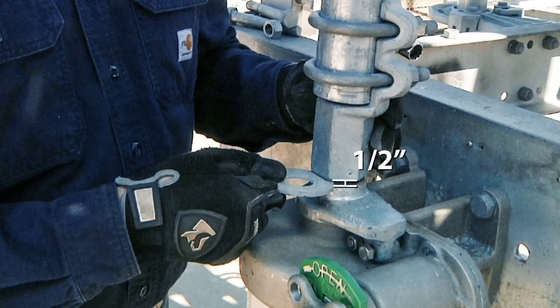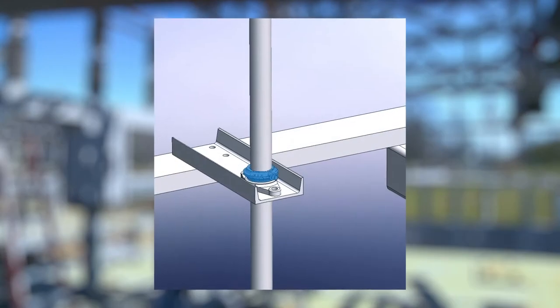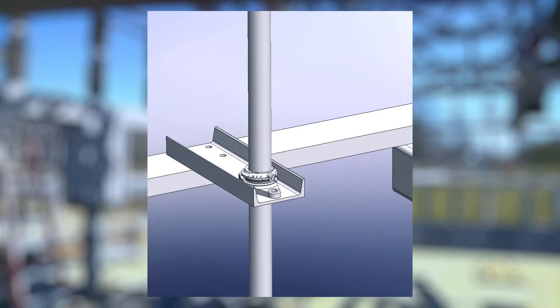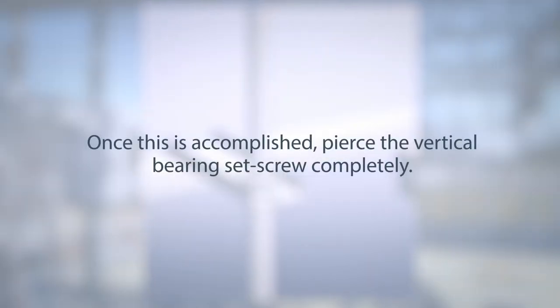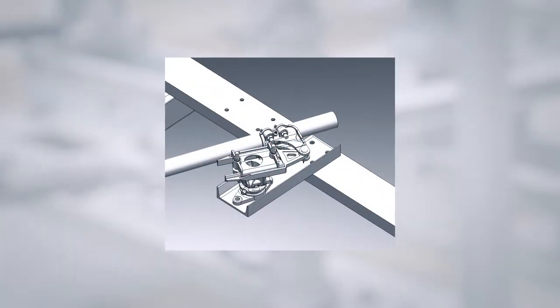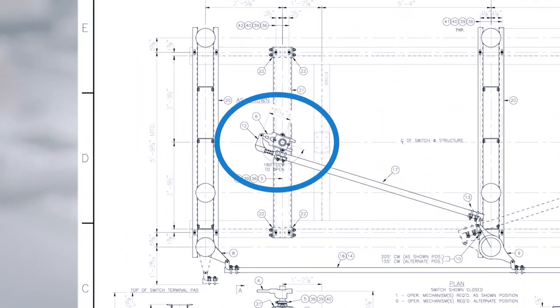The half-inch gap can be achieved by lifting the vertical pipe and torquing the vertical bearing collar. At this point, the bearing should bear the entire weight of the pipe. Once this is accomplished, torque the vertical bearing set screw completely. This will be the only torquing until final check and energization of the switch. Next, install the adjustable arm. Verify the lever arm dimension matches what is shown in the drawing package.